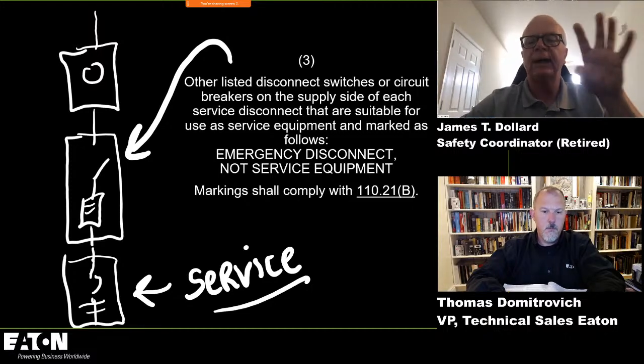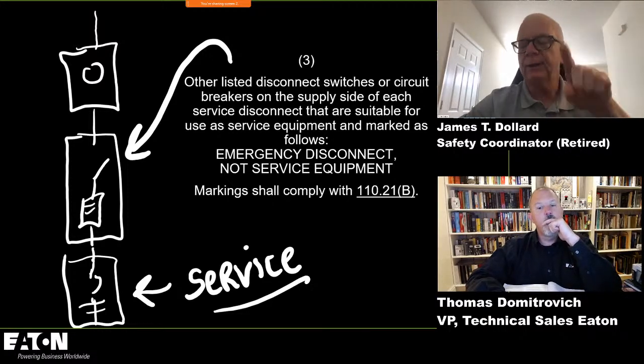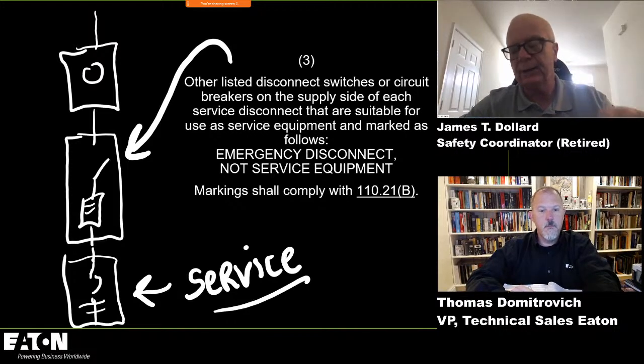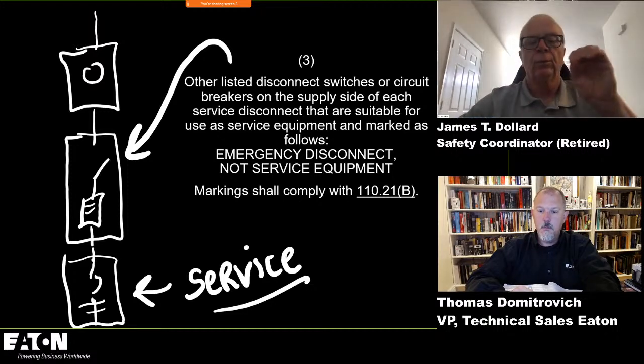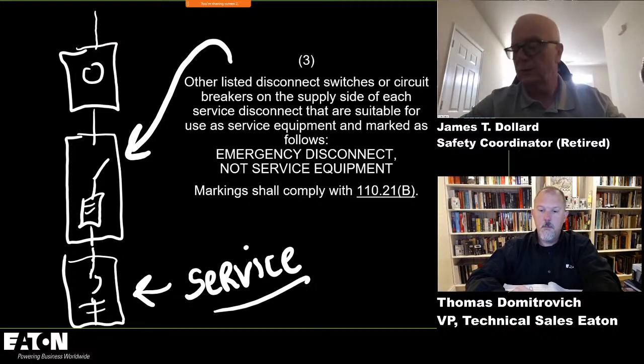Now, if we told you that had to be service equipment, you would need to get the grounding electrode into that enclosure, and you can't take SE cable into the home. You need to take SER. One of the reasons we went down this road is that we realize it doesn't need to be a circuit breaker. It could just be a molded case switch, which is probably where manufacturers are going to end up going, because it's cheaper. But if it's got a level of overcurrent protection in it, all the better.